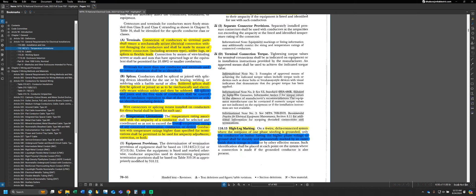The code does go on to say that conductors with temperature ratings higher than specified for terminations can be used for ampacity adjustment, correction, or both. In our scenario — where a conductor is rated for 90°C but must be terminated at 60°C — if other factors affect the ampacity, such as ambient temperature or the number of current-carrying conductors in the same raceway, we would be allowed to apply an adjustment based on the 90°C ampacity. The main point is understanding that conductors have different temperature ratings based on their insulation, and that affects how much ampacity we're allowed to use.